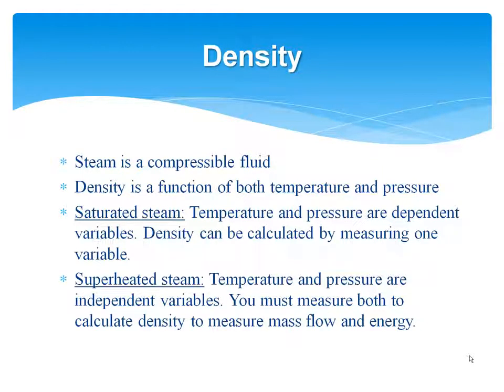So getting back to the density side, steam is a compressible fluid, and so density is a function of both temperature and pressure. So there's some additional measurements that need to be made along with the flow measurement. The little caveat there is in saturated steam, temperature and pressure are dependent variables, so you can measure one and still be able to calculate density. And in superheated steam, temperature and pressure are independent, and so you've got to measure both. Again, another little caveat here is in saturated steam systems, you do have to be a little careful. There are areas where you get unintended superheat, typically downstream of PRVs, and if you use a single sensor measurement, that can result in an inaccuracy in the measurement. Slide, please.